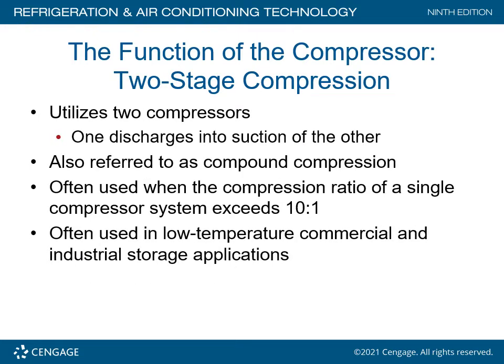Two-stage compression utilizes two compressors, where one discharges into the suction of the other. It is also referred to as compound compression. It is often used when the compression ratio of a single compressor exceeds 10 to 1, and is commonly used in low-temperature commercial, industrial storage, or cryogenic applications.